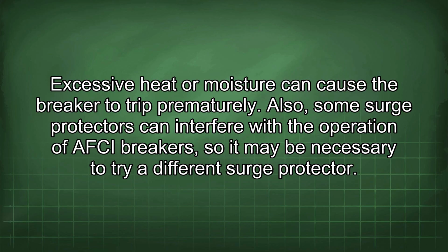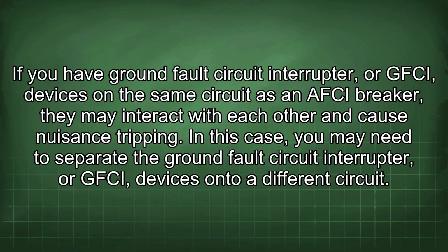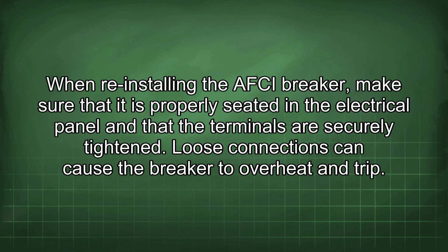Also, some surge protectors can interfere with the operation of AFCI breakers, so it may be necessary to try a different surge protector. If you have ground fault circuit interrupter or GFCI devices on the same circuit as an AFCI breaker, they may interact with each other and cause nuisance tripping. In this case, you may need to separate the ground fault circuit interrupter or GFCI devices onto a different circuit. When reinstalling the AFCI breaker, make sure that it is properly seated in the electrical panel and that the terminals are securely tightened.